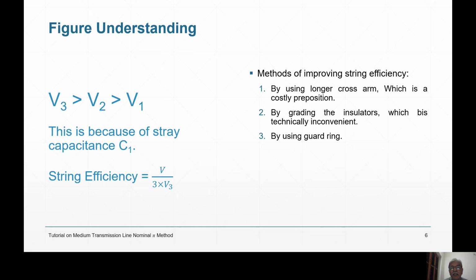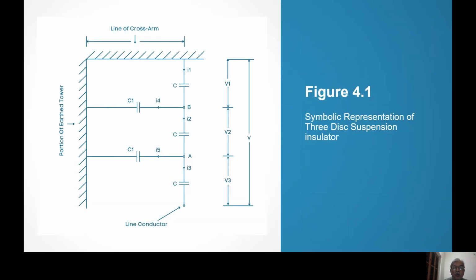So there are three remedies. The first remedy is you reduce the stray capacitance to such a low value that the difference between V3 and V2 becomes negligibly small, even though V3 is still more than V2. For doing that, you increase the distance between the string and the earthed tower, and for that you have to increase the length of the cross arm.